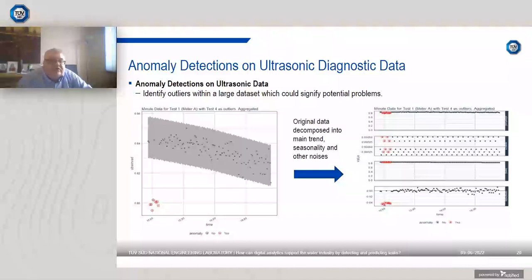The output of this project has demonstrated the potential for end users to increase operational efficiency through harnessing the data. This data is already available to them through most standard ultrasonic transmitters, and equipped with the ability to identify a specific fault, there is no longer a need for end users to shut down production, remove the meter from a pipeline, and conduct multiple diagnostic tests before the solution can be found.